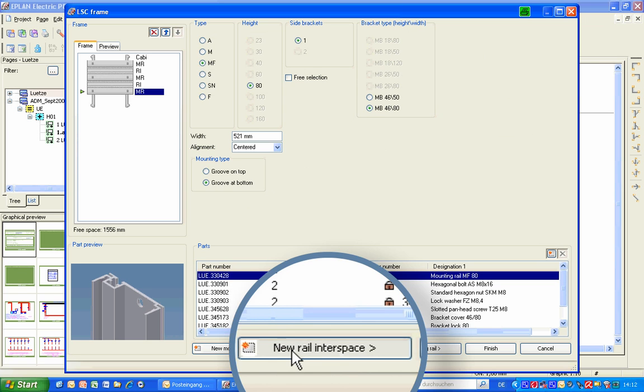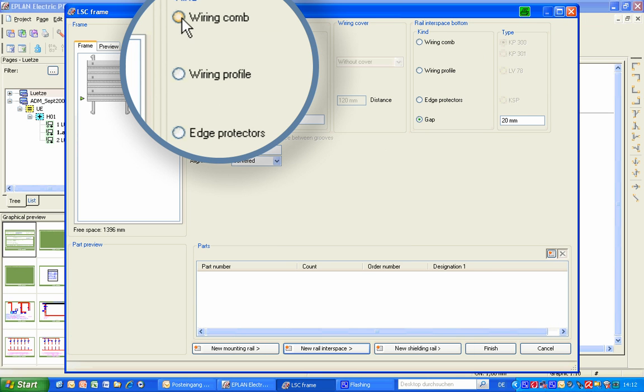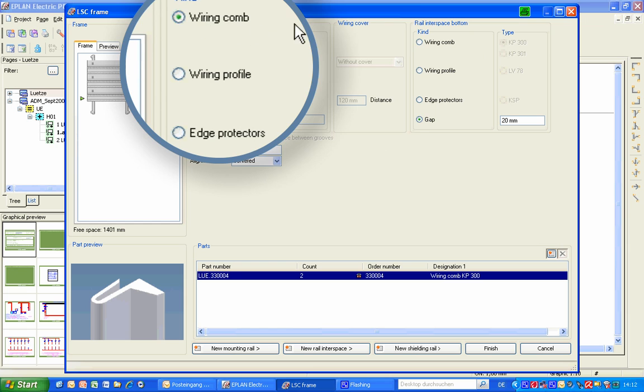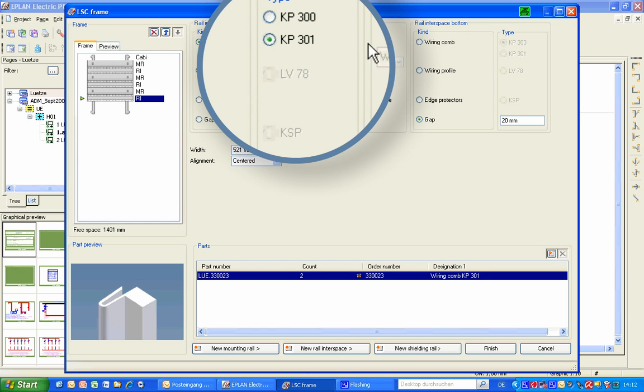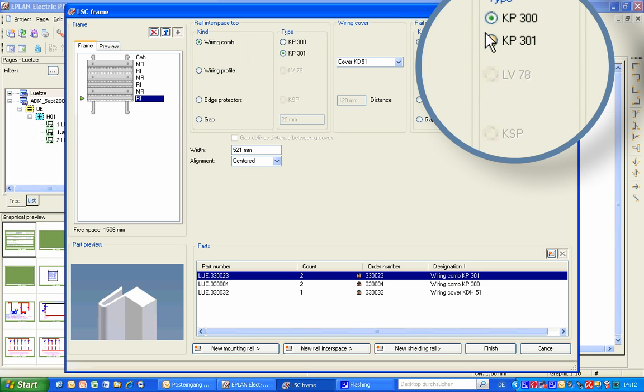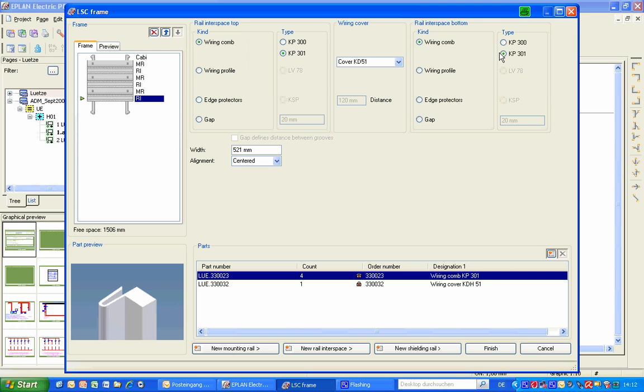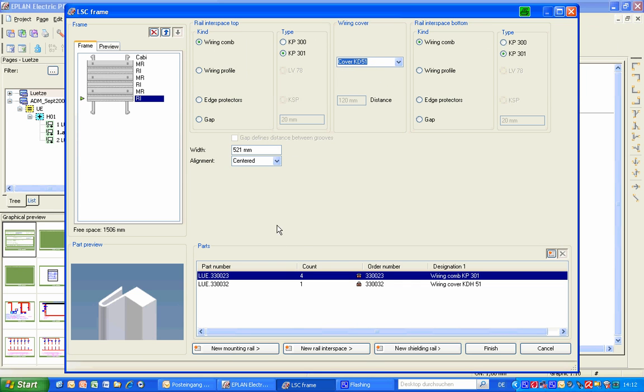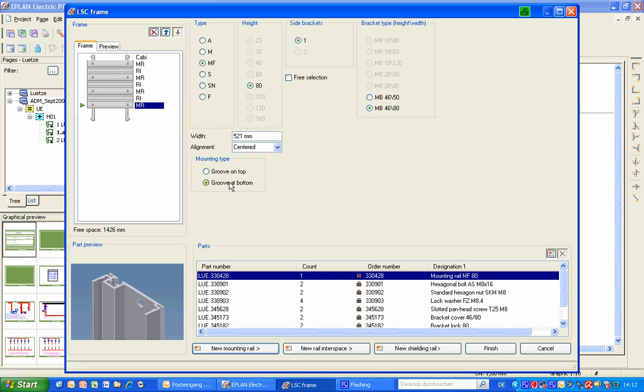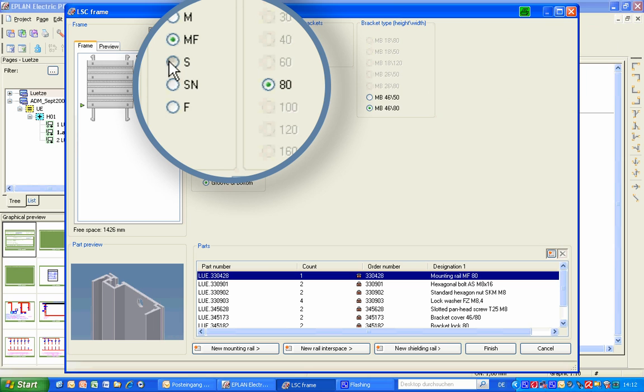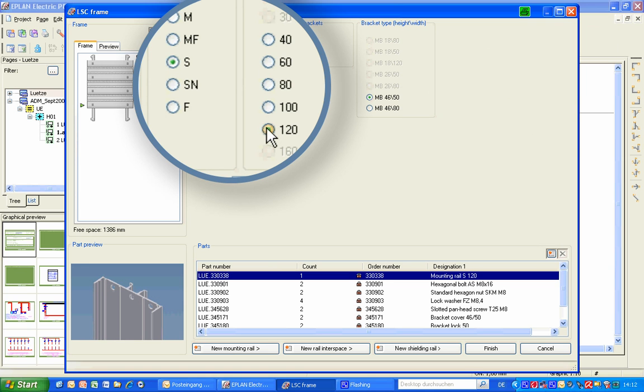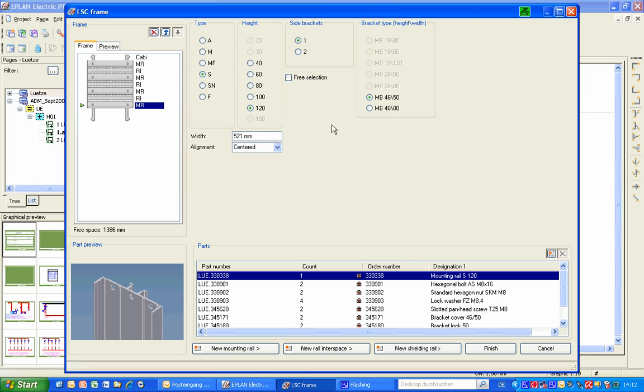A new rail interspace. Wiring comb on top: type KP301. To the following rail, again a KP301. This comb type is chosen because conductor wires with a cross section of more than 2 square millimeters will be used. The following mounting rail is S, for a high DIN rail 120 millimeters wide — for instance, for mounting correspondingly high power supply units.